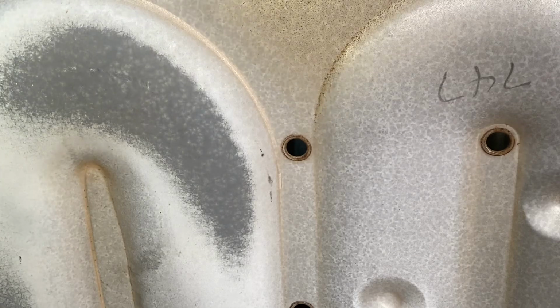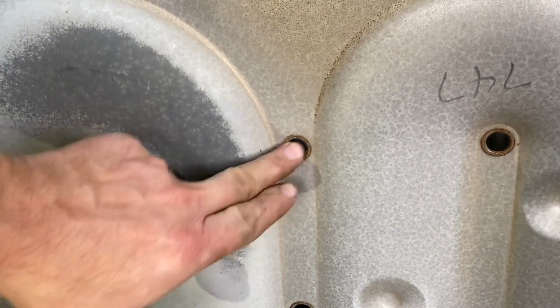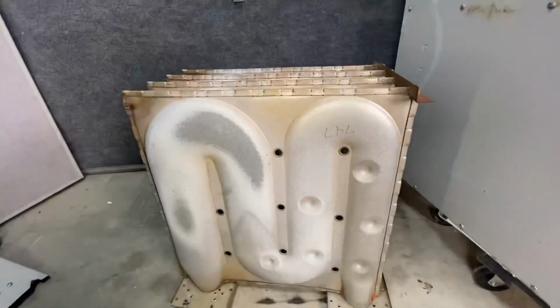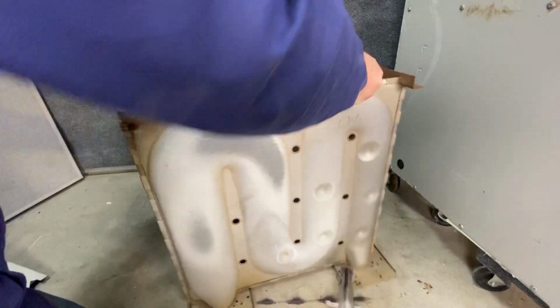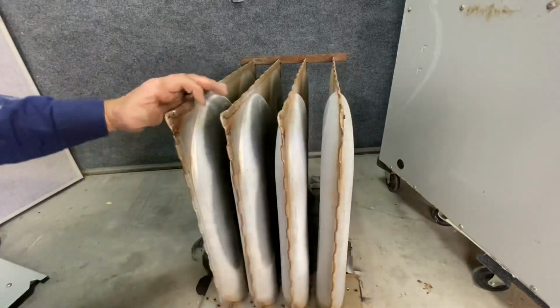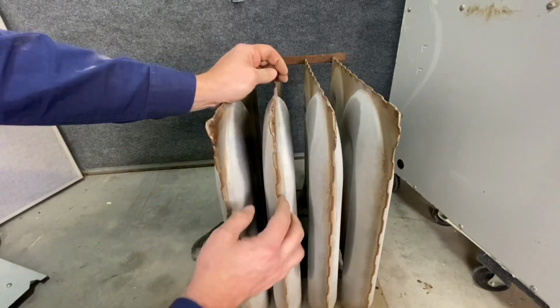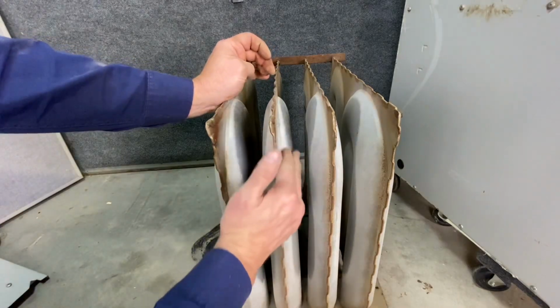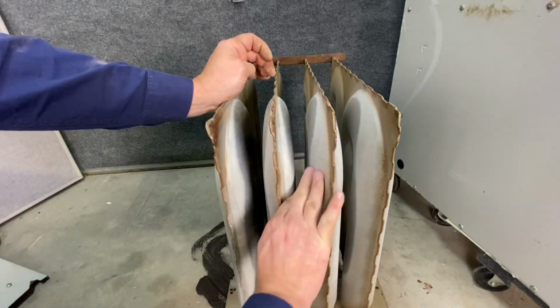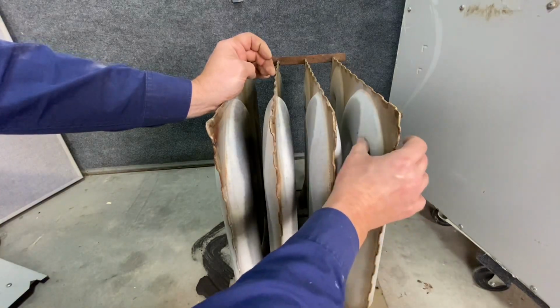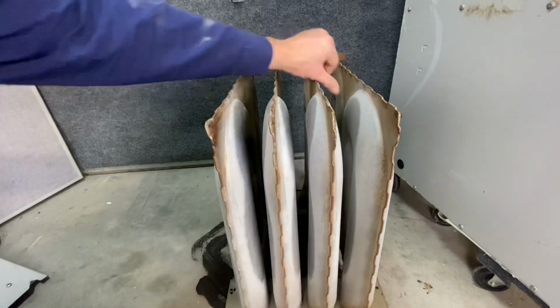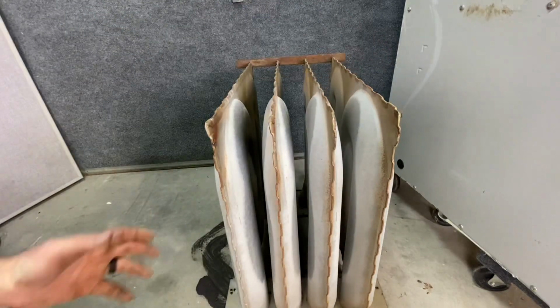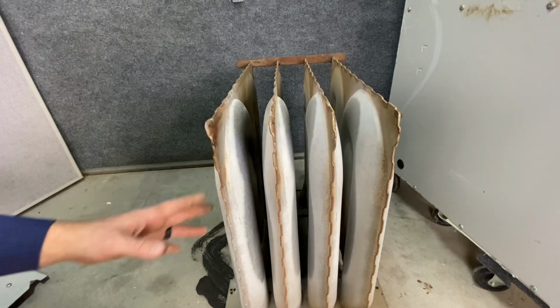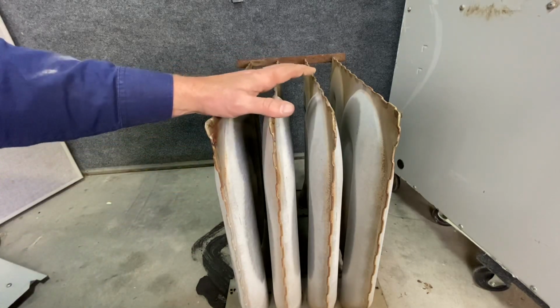I didn't see an actual hole in any particular one of the tubes, but there's a lot of buildup inside. And notoriously, they're used to leaking right around these connections right here. So I don't see anything specific yet. As we turn this, any one of these seams right through here, especially right here at the ends, are notorious for burning out, especially if the gas pressure wasn't set right. They'll overfire and burn out. We have some rust spots inside of there. We got some damaged spots here. What I'd really like to do is put my endoscope in there and see what it looks like on the inside, but it's so black and charred that it'd be really difficult to see.